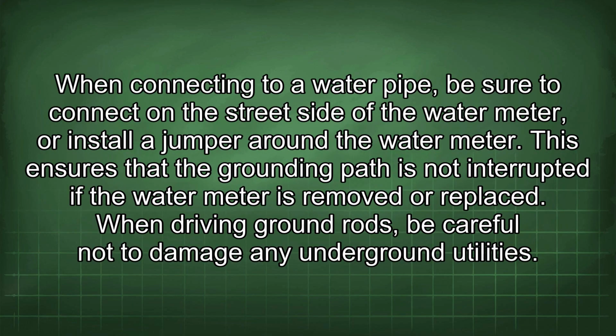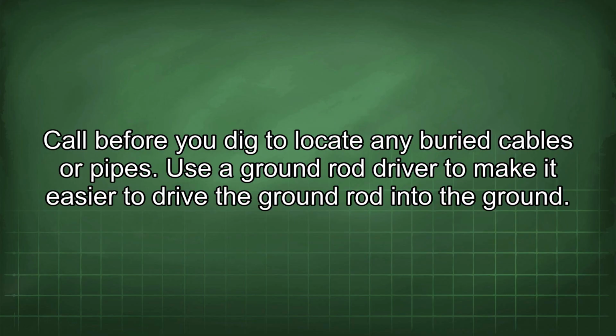When connecting to a water pipe, be sure to connect on the street side of the water meter or install a jumper around the water meter. This ensures that the grounding path is not interrupted if the water meter is removed or replaced. When driving ground rods, be careful not to damage any underground utilities. Call before you dig to locate any buried cables or pipes.